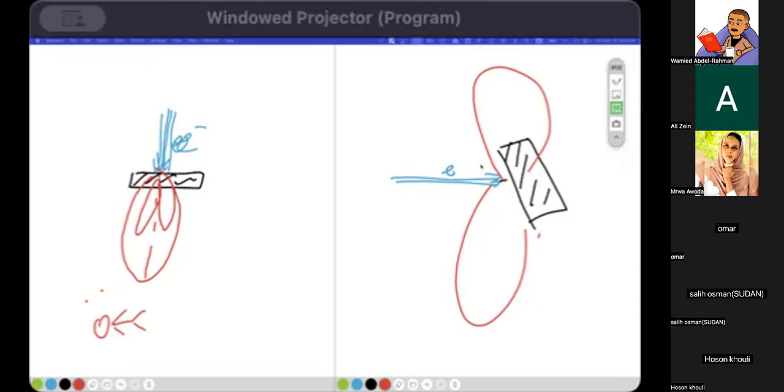It's more about the PDD curve. Anything that can affect the electron energy, I think you have to do a quality assurance on the beam. So my suggestion is just check a PDD 10 by 10. You don't need to recommission. Just check for a 10 by 10 field. Look at the symmetry, look at the flatness. This is what we do whenever we have something related to the beam, for example changing the target, changing a flattening filter, changing whatever. We will do this check.